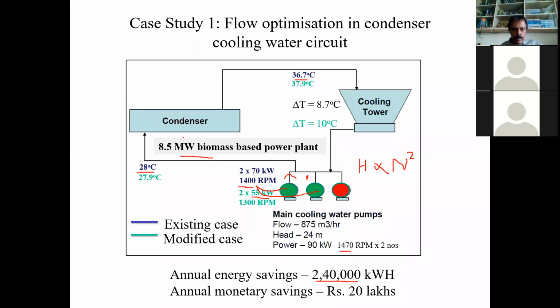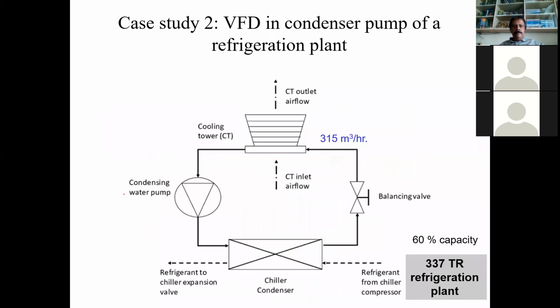At the same time, we have to ensure that the vacuum in the condenser is not disturbed. There's one important parameter which has to be simultaneously monitored. As you reduce the flow rate, there is a possibility that the vacuum is affected, so you keep on reducing. At one point, you find the condenser vacuum going up, getting more pressurized, so you stop at that point. And that is the point given by this 1300 RPM. Okay, this is one. And a similar case here.